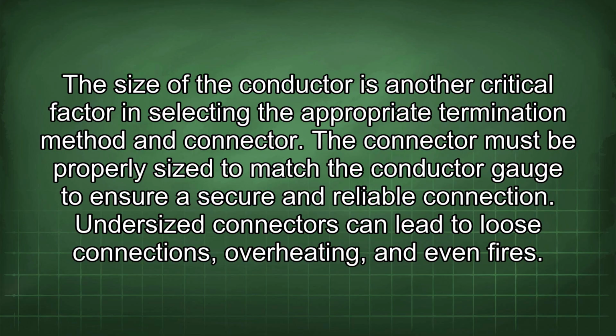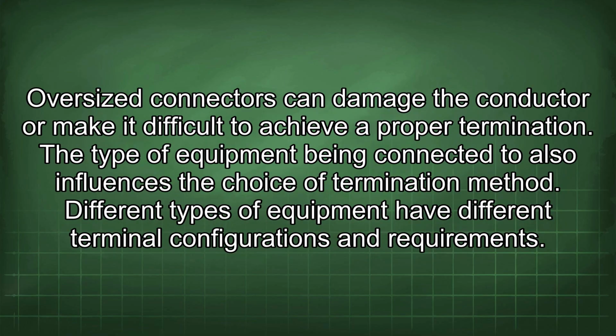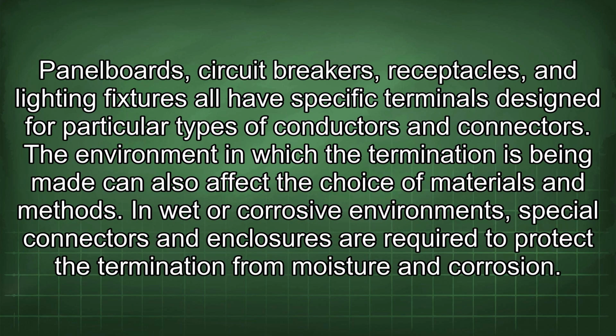The size of the conductor is another critical factor in selecting the appropriate termination method and connector. The connector must be properly sized to match the conductor gauge to ensure a secure and reliable connection. Undersized connectors can lead to loose connections, overheating, and even fires. Oversized connectors can damage the conductor or make it difficult to achieve a proper termination. The type of equipment being connected also influences the choice of termination method. Different types of equipment have different terminal configurations and requirements. Panel boards, circuit breakers, receptacles, and lighting fixtures all have specific terminals designed for particular types of conductors and connectors.